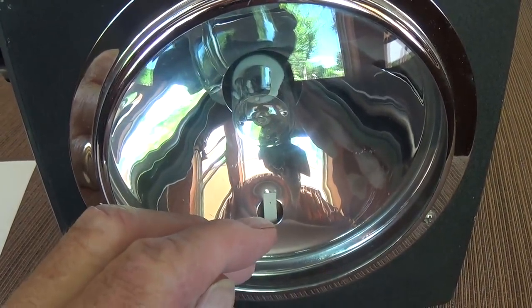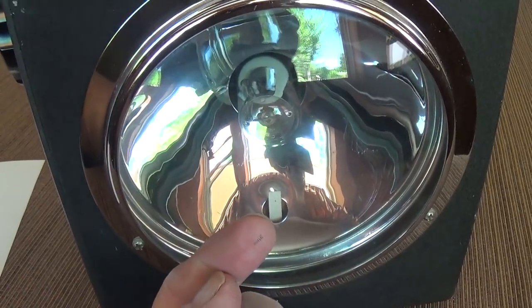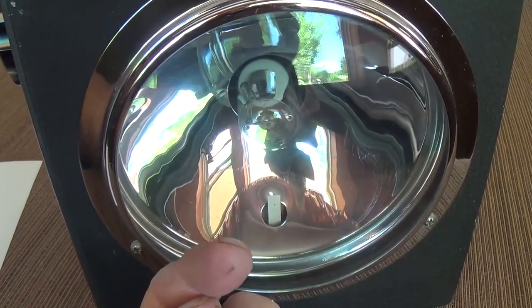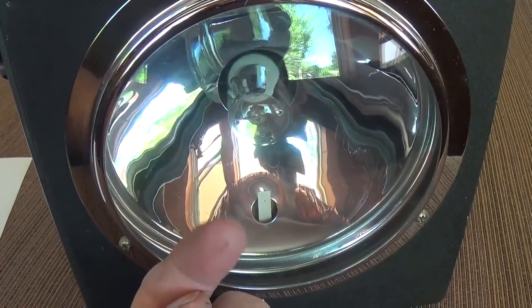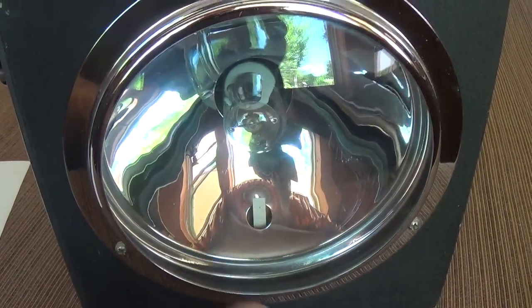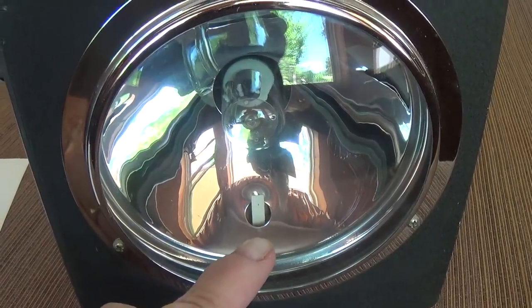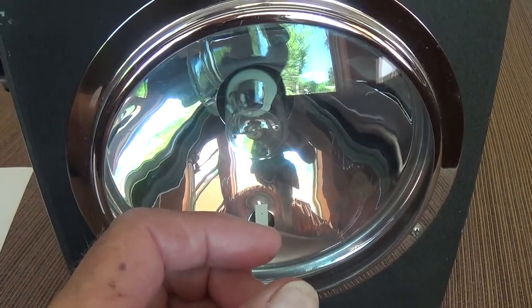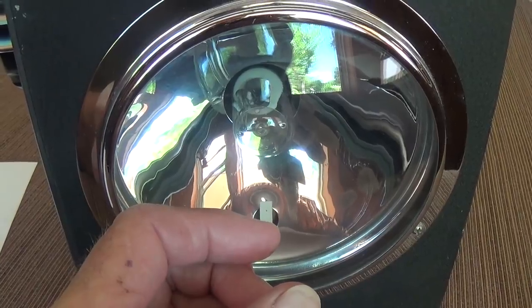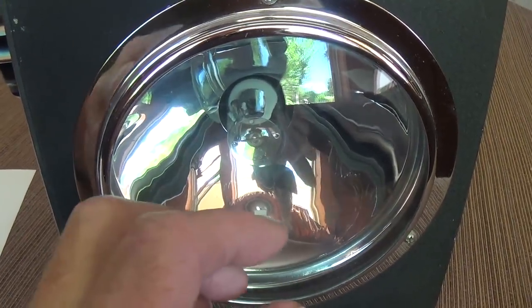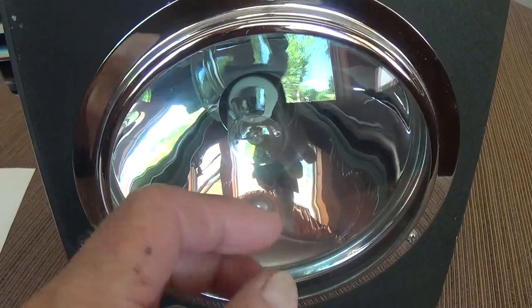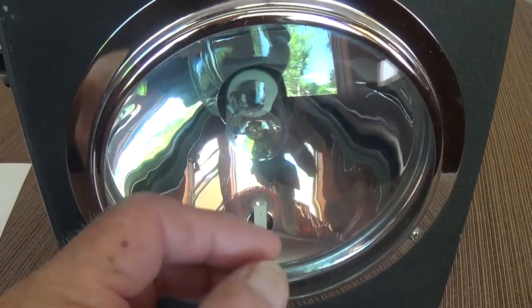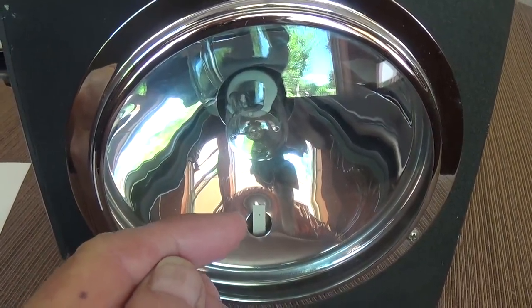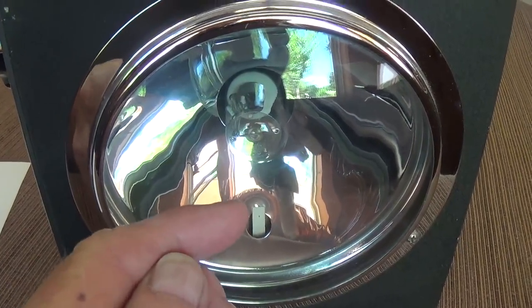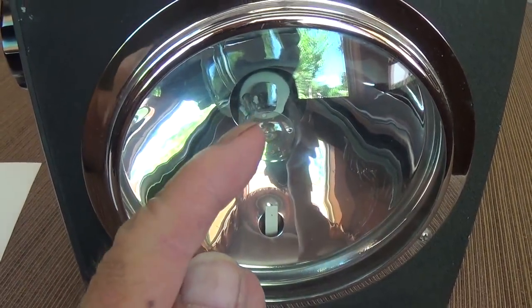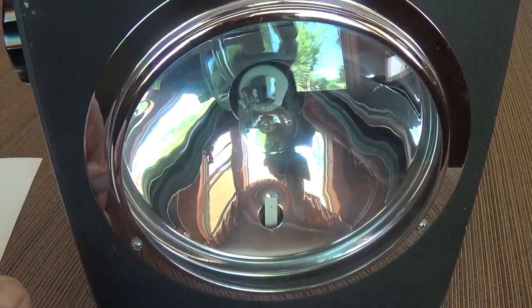Down there at the bottom, we see this leaf. Now, the leaf is for calibrating purposes. It's going to oscillate back and forth at 3,600 beats per minute. Why? Because it is operated off of an electromagnetic coil that is connected to wall current. And the polarity of the coil is going to change 60 times per second, which is going to make the little leaf beat at 3,600 beats per minute. We're going to use that to calibrate the strobe, as you will see shortly.